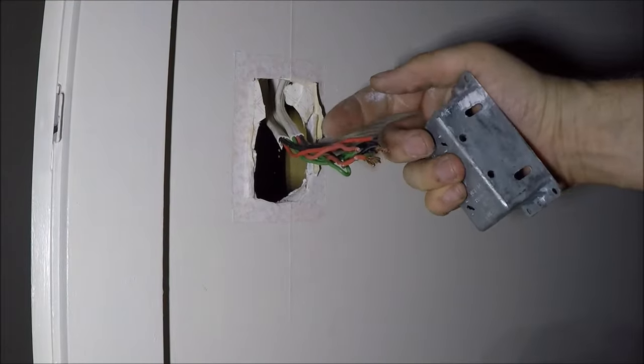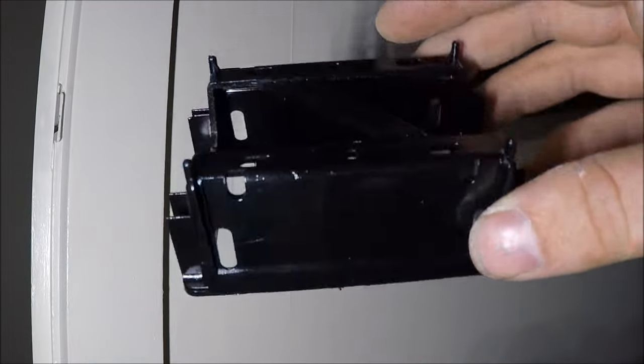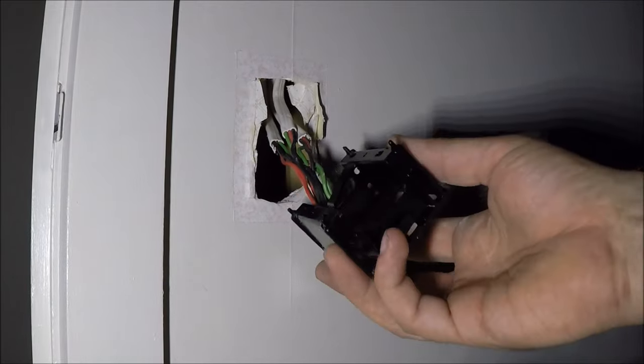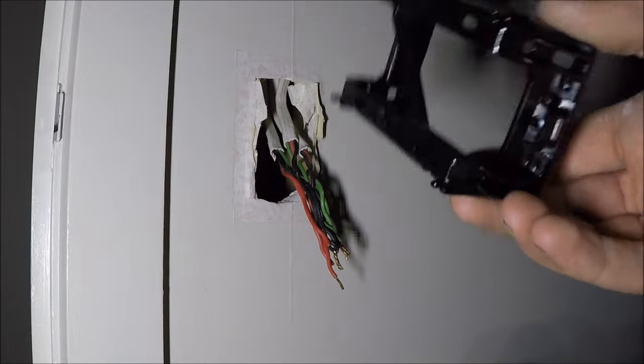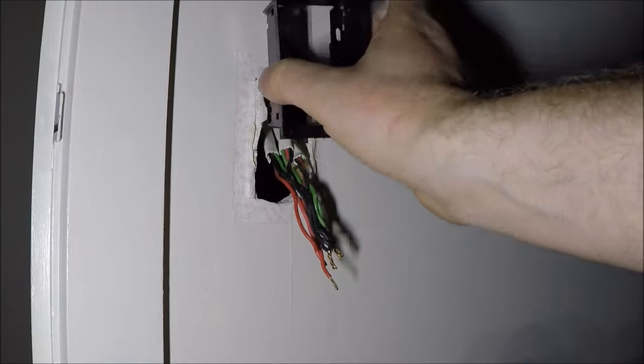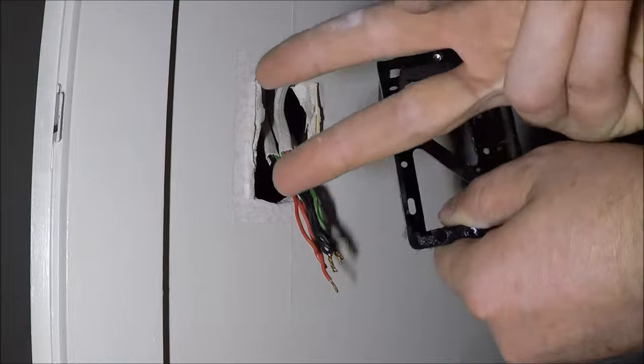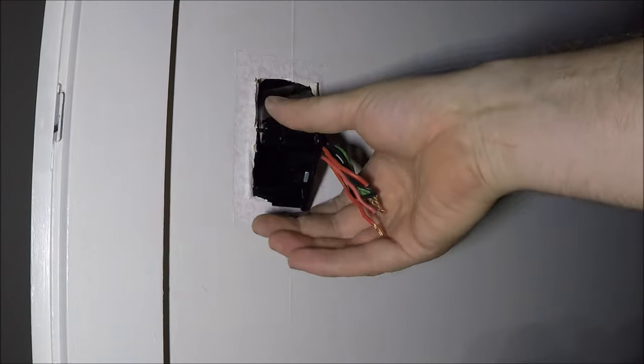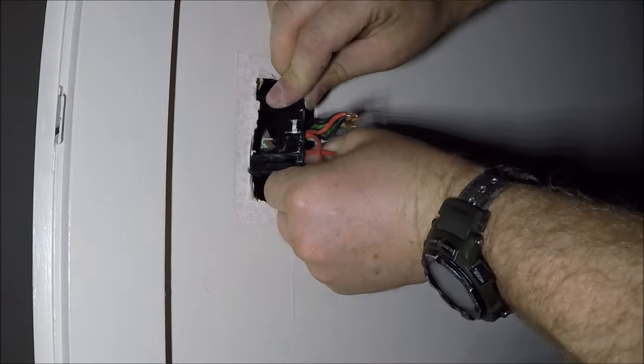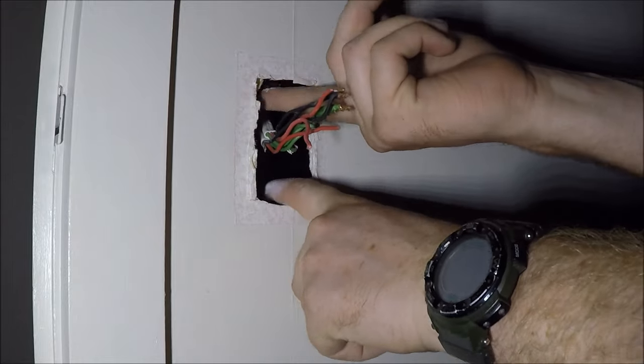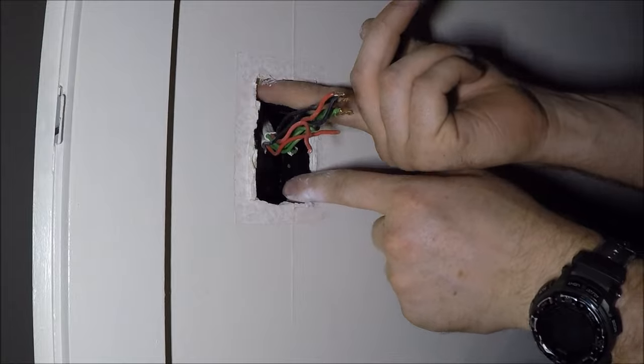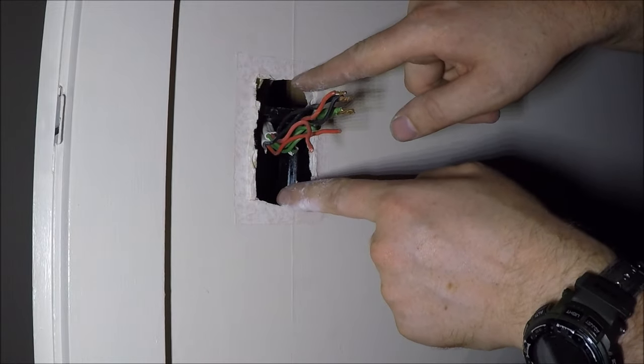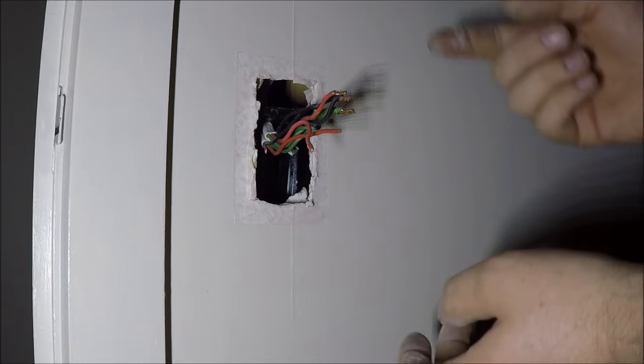This here is a plastic flush box. Every time I replace a switch or socket, I always put one of these plastic ones in nowadays. So to get them in the walls, it's pretty simple. You put them in sideways like that so you can get them inside the wall. Once they're in the wall, you rotate them, and then screw two screws in the side into the stud. Make sure you keep these cable ends outside of the wall so you don't lose the flush box down inside the wall. So slip it in like that, then rotate it. Make sure you can see these wee screw holes that the screws go into and just line one up with the bottom one at the top so you can actually visibly see them. If you can't, get a wee jib saw in here and just cut a wee notch out of the jib.